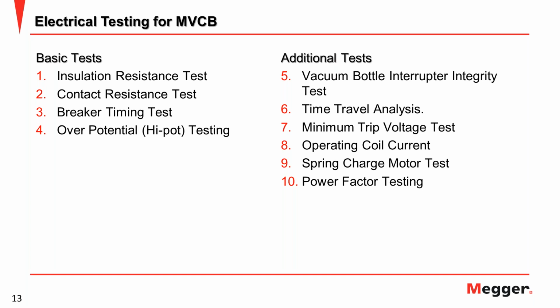Mostly the service companies do these tests as basic tests, and normally they also provide or ask you for additional testing like vacuum bottle interrupter integrity test, time travel analysis, almost the same as the breaker timing but more detail. Regarding detecting mechanical issues, as you know from the previous slide, the mechanical component gives a high percentage. This is why time travel analysis is very important to be tested on the MV circuit breaker. Minimum trip voltage test, operating coil current, spring charge motor test, and also some operators do power factor testing. But I think on medium voltage it is very rare. So normally only up to number 9, the spring charge motor test.